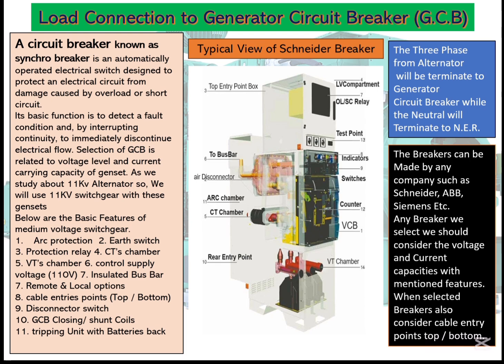Breakers can be supplied by Schneider, ABB, but any local vendor can provide you a breaker. But before we install a breaker, we should look at the specification, whether it meets the alternator we have: ampere rating, voltage rating, then some protection. So if the breaker is equipped with that, we are good to go.